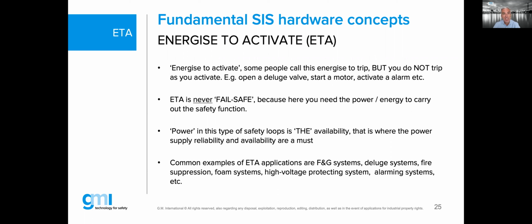Again, for the simplicity of this webinar, I call this here ETA, not to be confused with the event tree analysis. That's another ETA which you may have come across in some lectures, books, etc. So energized to activate, ETA, is never fail-safe. If you think about it, if your control platform has an internal failure and you cannot turn on the digital output module of that PLC, how can you call this fail-safe? That's why those type of modules are never called fail-safe.